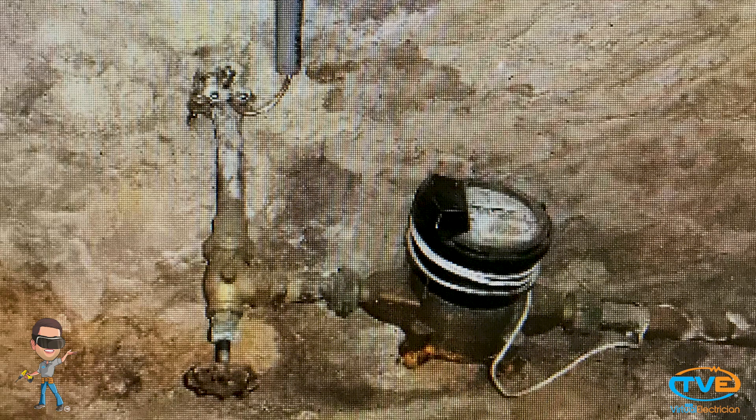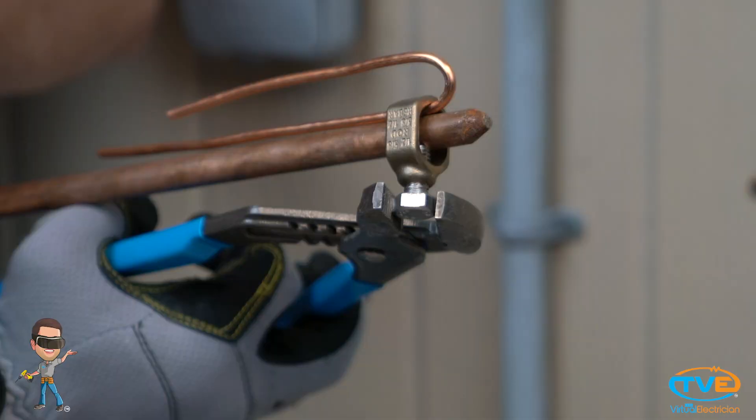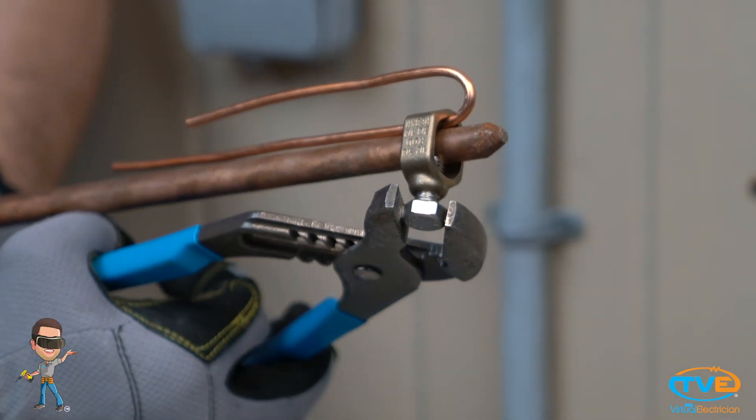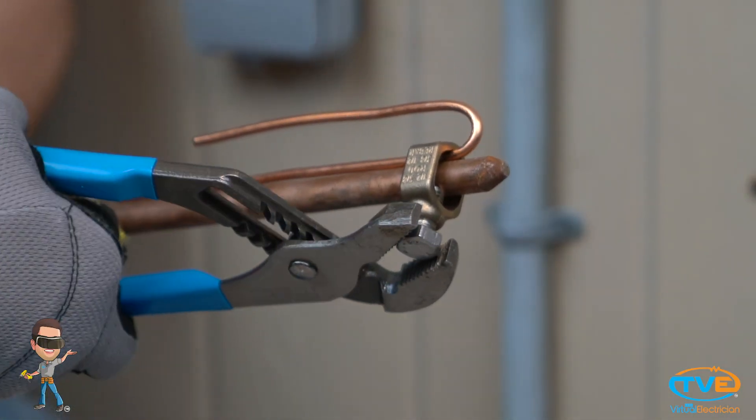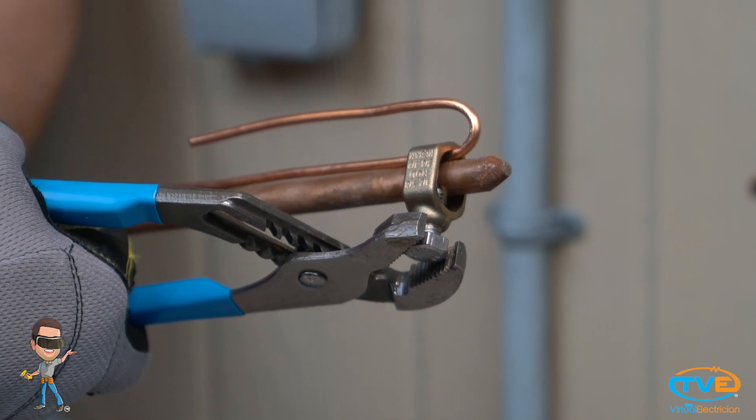First, you want to make sure your old panel is up to code. Make sure you have a ground and a supplemental ground. If you only have one means of ground at your panel, you will need to add a ground rod outside to get your supplemental ground. If you have two grounds, you can move on to the next step.